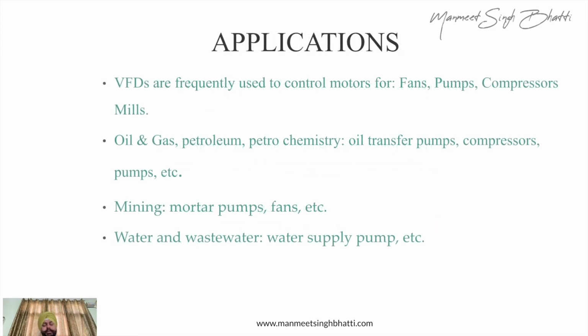Now coming to the application where we can install, as I've explained earlier also, VFDs can mostly be installed on fans, pumps, compressors, any kind of crushing mills. Wherever you want to, you can install that. Basically any motor, any rotating machinery where you are using an electrical motor, you can actually put in a VFD. But the catch over here is, if that VFD is going to control some kind of voltage, some kind of load, some kind of frequency, only then you should go for a VFD. It is not required that if you are not controlling anything, then you put a VFD. It's always better that you control it. You may reduce the speed by maybe 5%. That 5% is actually going to get you some kind of a saving. So that is the reason for putting a VFD.